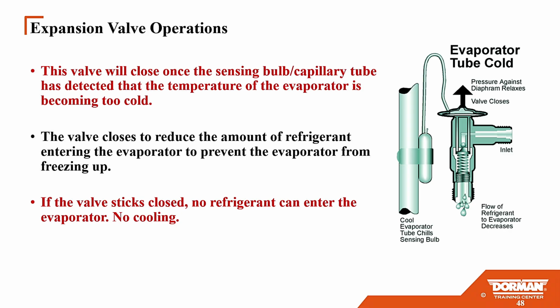Freeze up. Absolutely. Remember I said that, you need flow going through there. And of course, those of you that have changed evaporators, you've pulled them out with all sorts of crap and everything on it. Some little bit of misty oil that gathers every dirt and dust and everything else. Well, guess what? That freeze up and ice would be the same thing. So we're trying to maintain those, to prevent the evaporator from freezing.